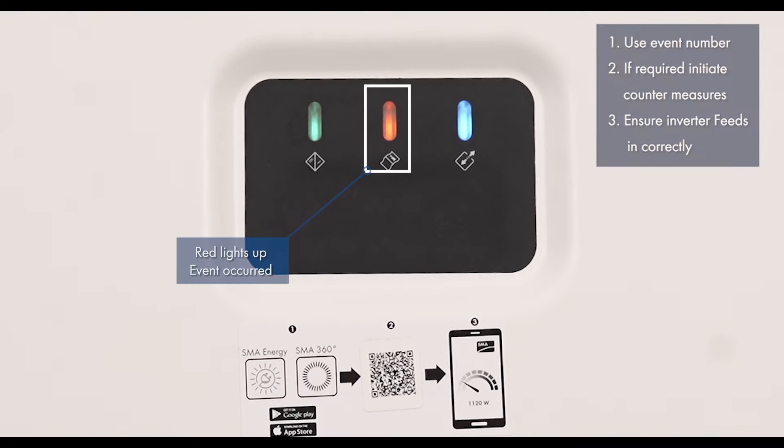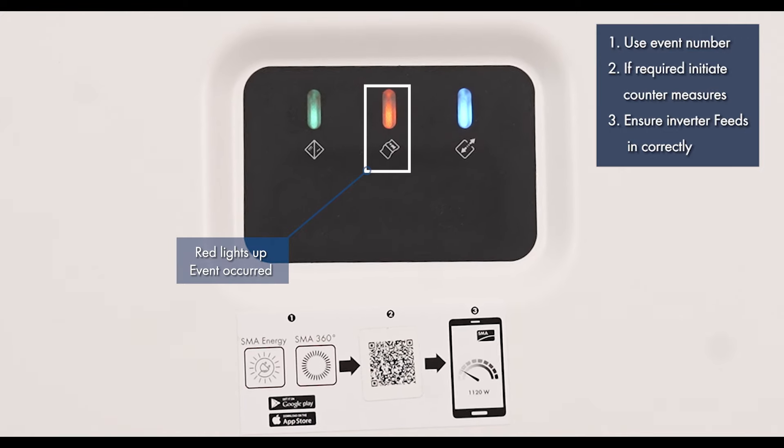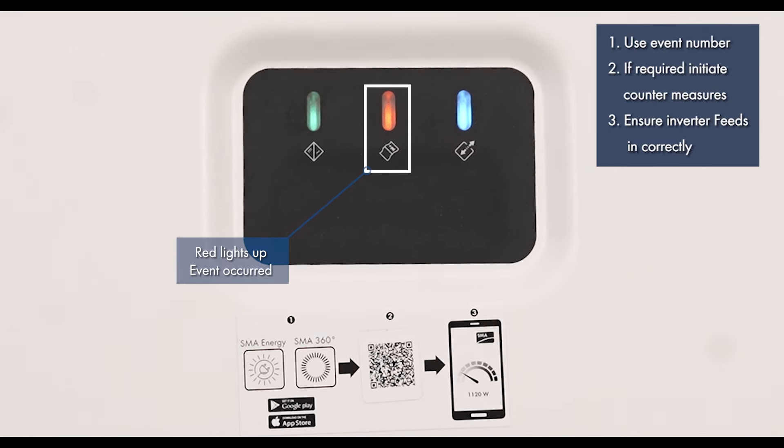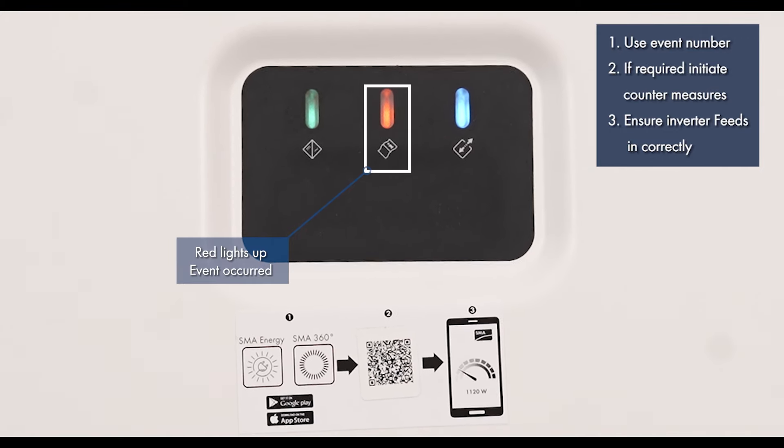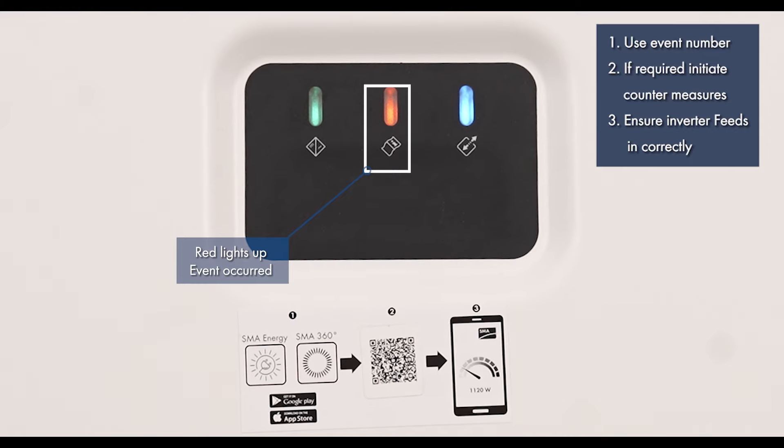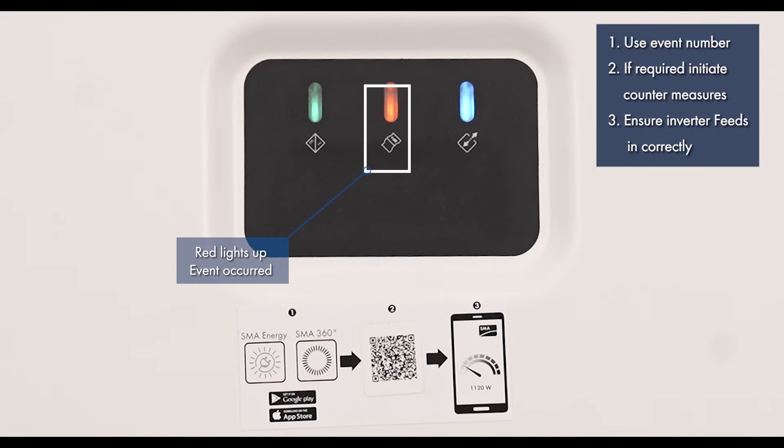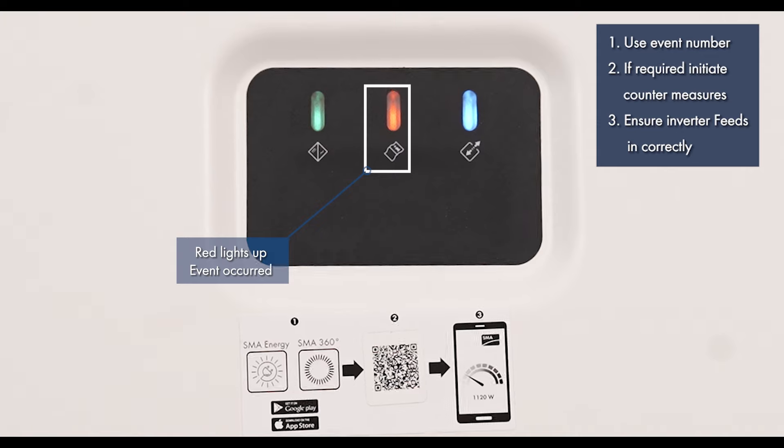If the red LED lights up, that means an event has occurred. In that case, use the event number to find out which event has occurred and, if necessary, initiate countermeasures. Ensure that the inverter feeds in correctly.